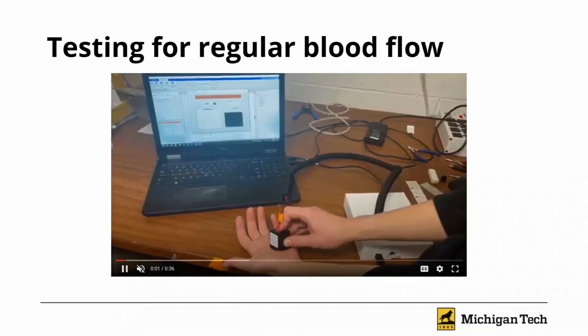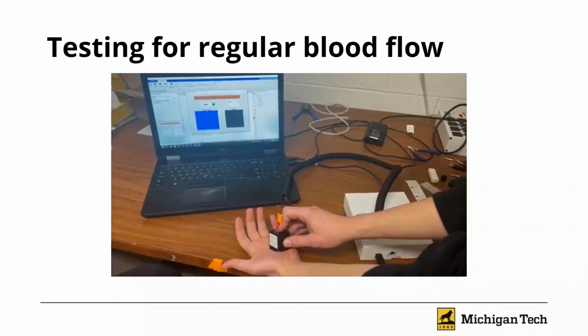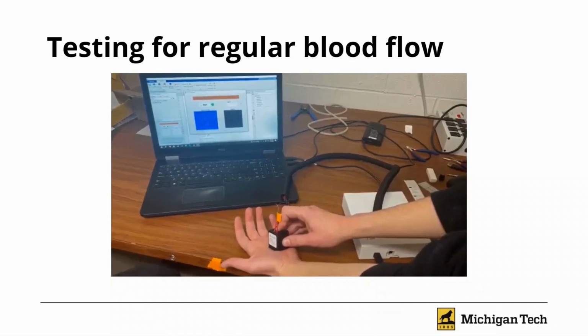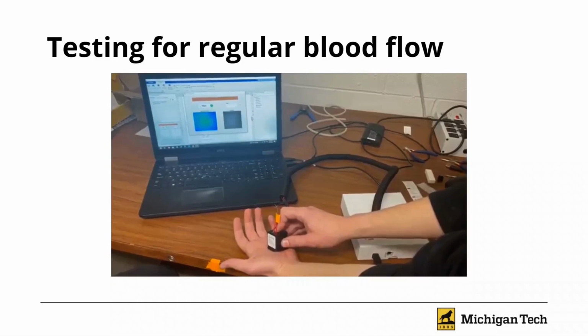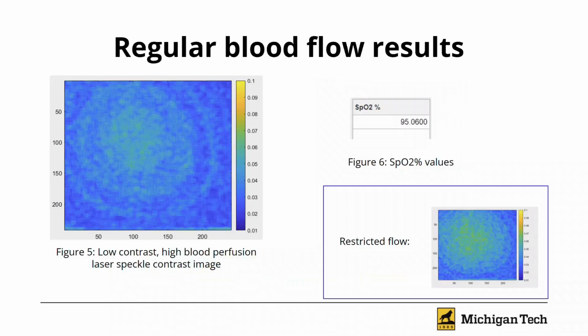We then restored blood flow to the hand by removing the exercise band. The probe was again used for a few measurement cycles. The output from the probe shows a noticeable change in both SpO2 and the contrast image. The SpO2 value has increased to 95%, which is within normal range. The image shows less of the color yellow, meaning the global contrast is lower, and therefore blood flow in the hand has increased.